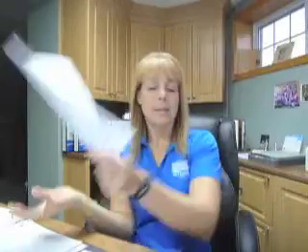So for example, if you need to clean out the wax bath on a monthly basis, unplug it, let the wax go hard, replug it in so that the wax starts to melt on the outside, unplug it again, take out that big hunk of wax, clean out the wax bath, put the wax back in, or change the wax if the wax is dirty. Hydrocollator, you would need to unplug it, let the water cool down, empty it, clean it out, refill it, plug it back in. Okay, just an example of some things to check monthly.